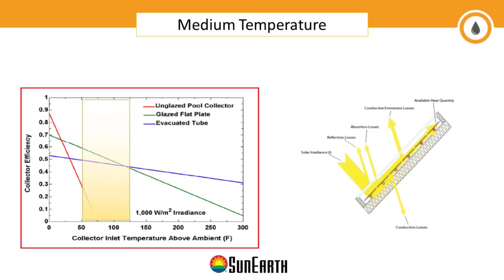There are different efficiency curves depending on the collector, based upon gross area, but they decline at different levels. An evacuated tube collector has vacuum insulation, so it can lose less heat with higher temperature differentials, giving it more of a flatter efficiency curve. It starts out a little lower because there's some loss in gross area between the tubes versus a flat plate, but it can carry out longer. There's a crossover point between the two technologies right around 125 degrees Fahrenheit differential between ambient and collector input temperature, usually around 180 degrees Fahrenheit application temperature. So we see a crossover in these two technologies, and you might start looking at one versus the other if you need those high temperatures.